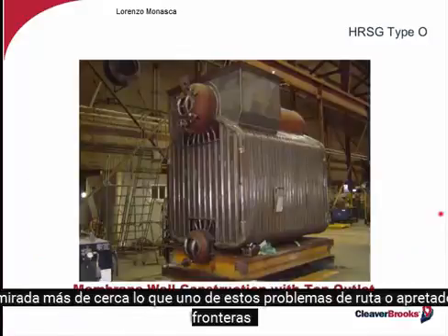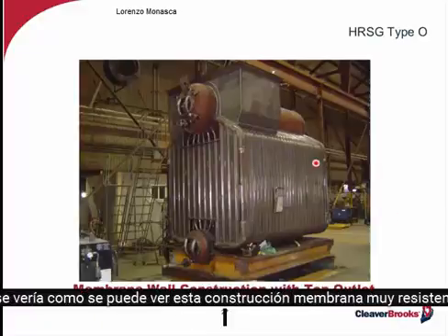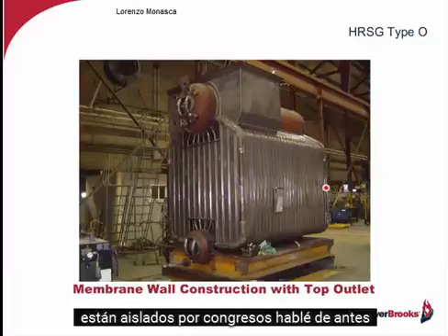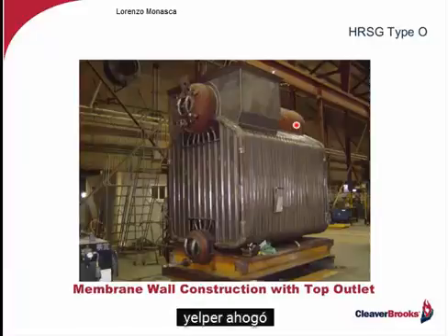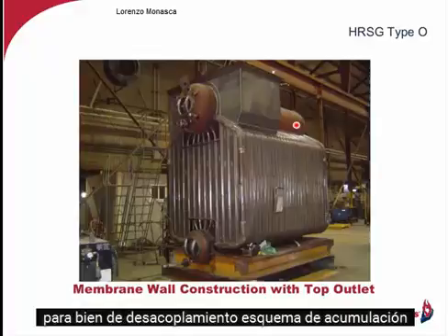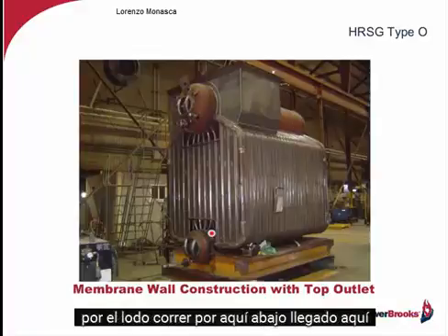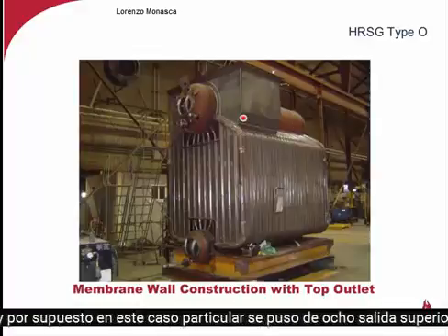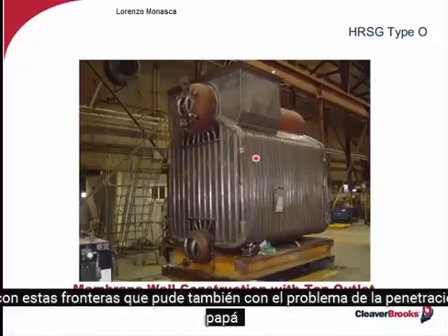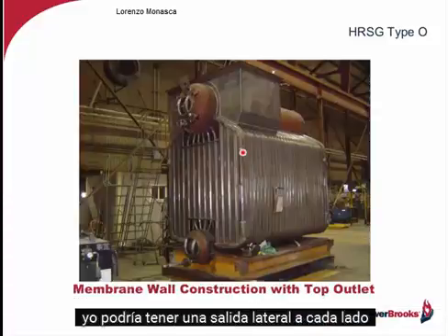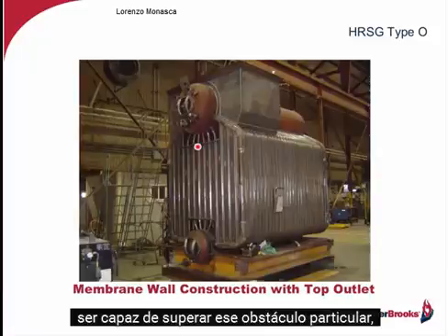A little closer look at what one of these drum-over-drum O-type boilers would look like. You can see this membrane construction, very rugged. Our isolated downcomers, as I spoke of before. The upper drum, large, for good steam disengaging and accumulation. My mud drum down here, downcomer here. And of course, in this particular case, it's got a top outlet. With these boilers, I could also, with that roof penetration problem, have a side outlet on either side to be able to overcome that particular hurdle.